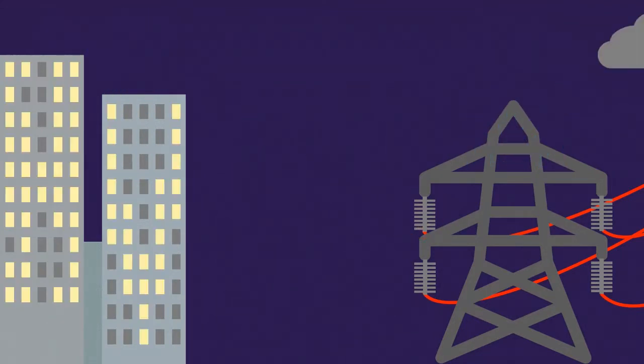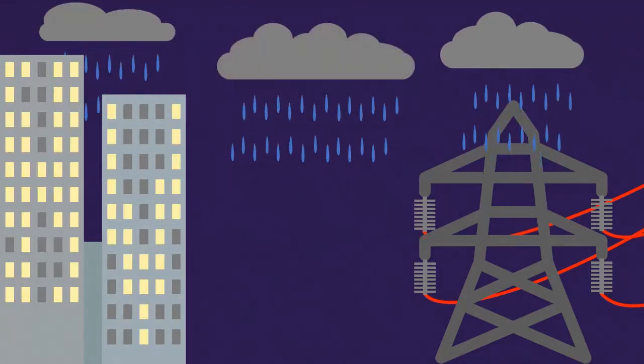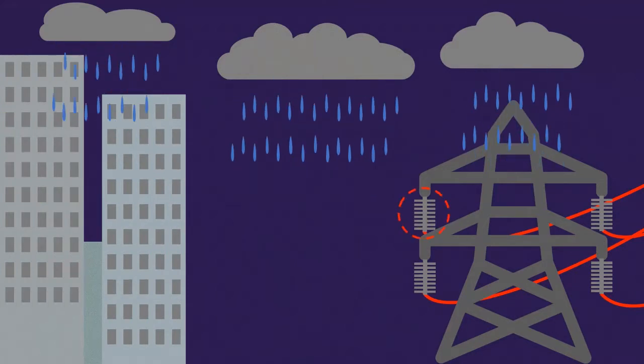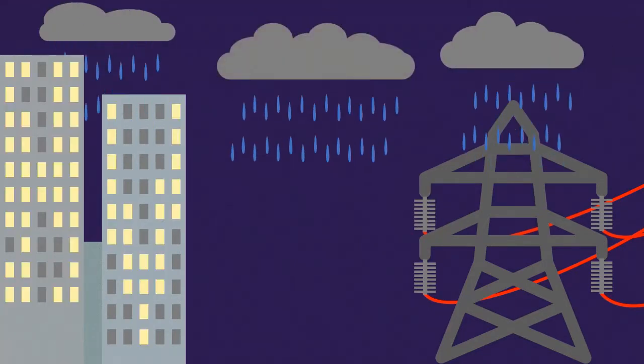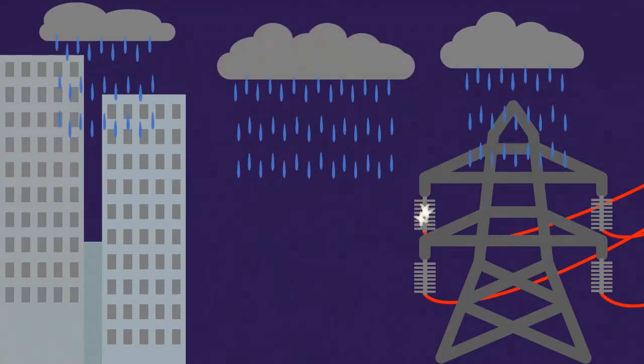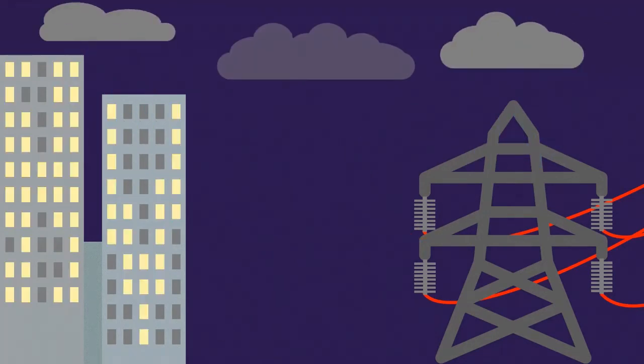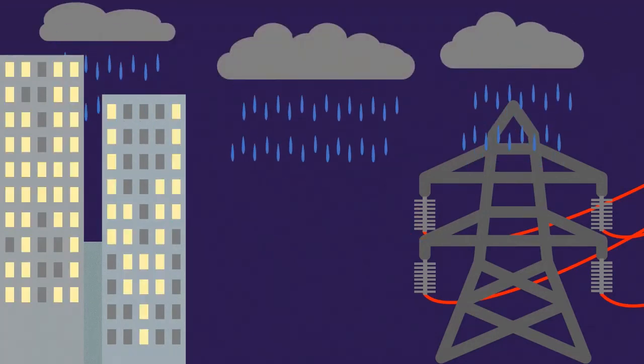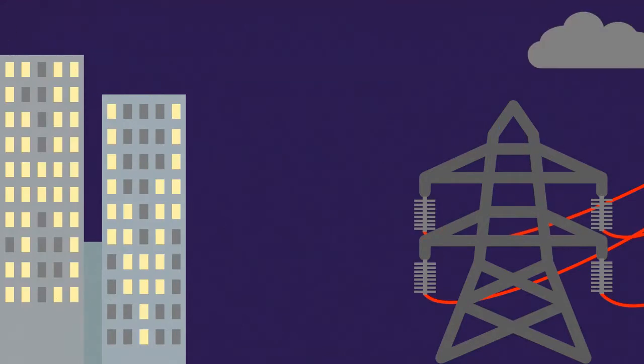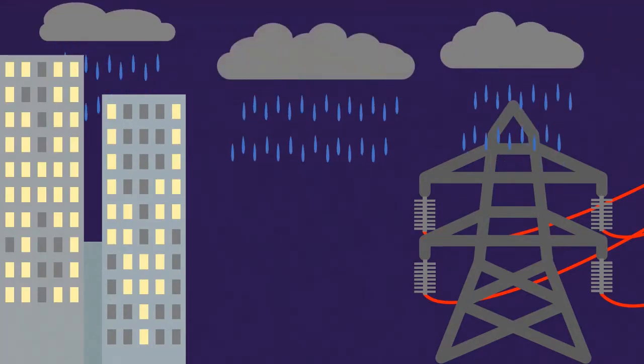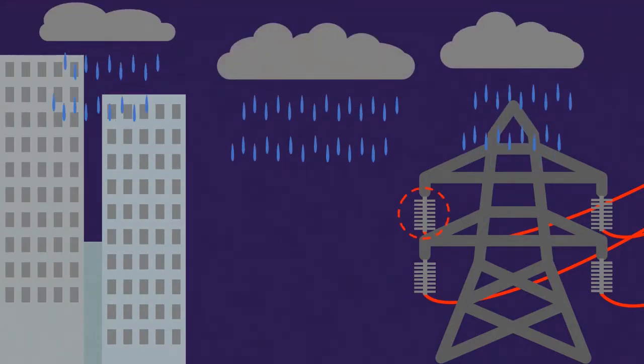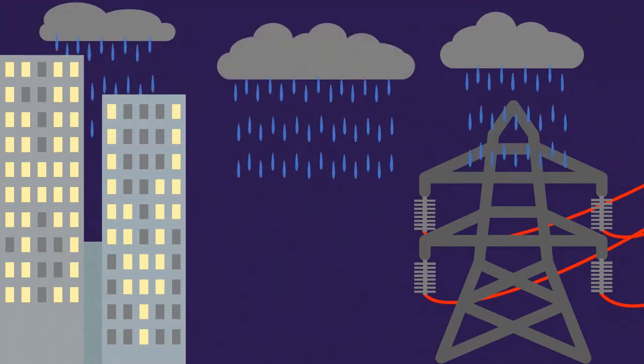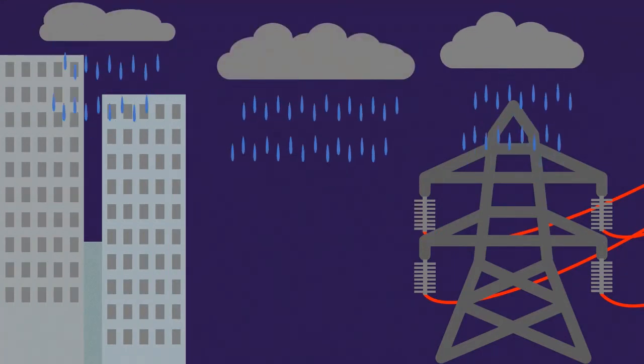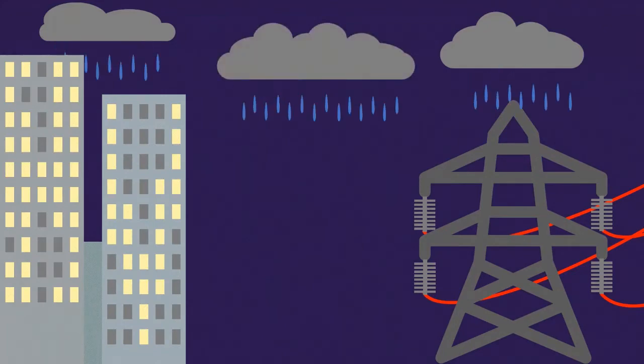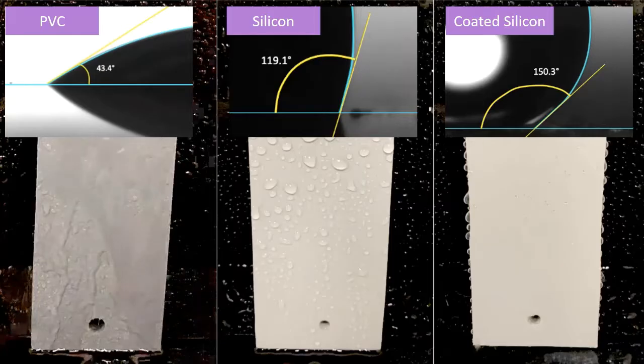Insulators are a key aspect of uninterrupted power transmission, commonly made out of ceramic, glass, and polymers, in particular silicon rubber. Silicon insulators are becoming increasingly popular due to their low cost, high dielectric strength, and hydrophobic properties, which help to decrease the occurrence of discharges. Discharges are caused by the production of conductive paths of moisture, leading to short-circuiting. This results in mechanical damage that builds up until physical failure and power outages.